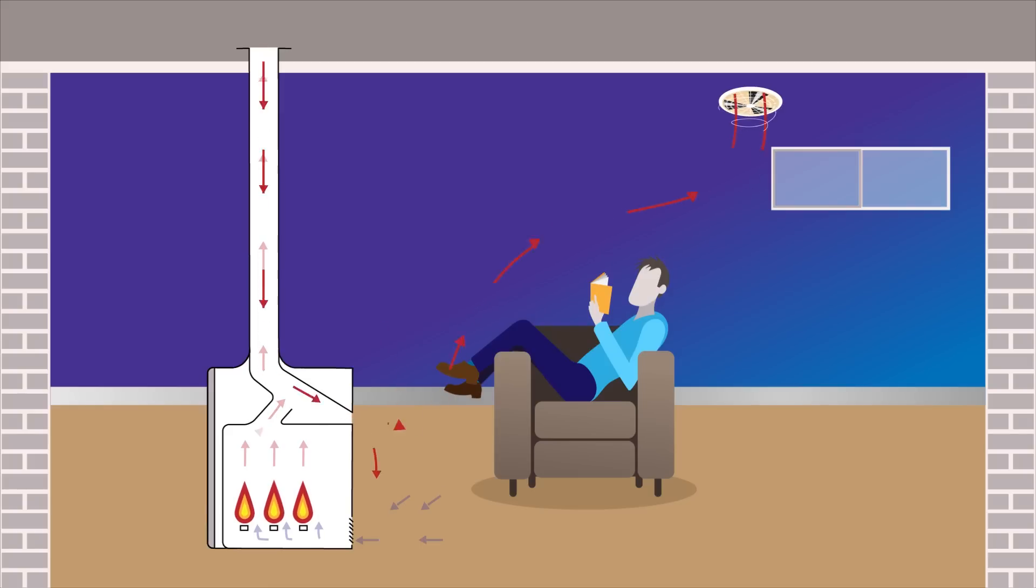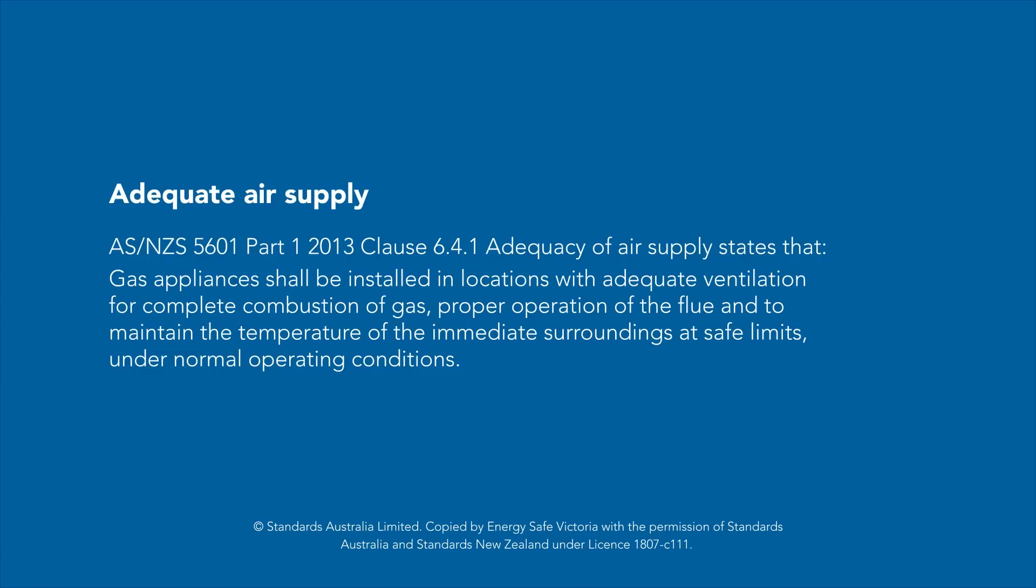This video explains what negative pressure is and its effect on gas appliances. AS NZS 5601 Part 1 2013 Clause 6.4.1 Adequacy of air supply states that gas appliances shall be installed in locations with adequate ventilation for complete combustion of gas, proper operation of the flue, and to maintain the temperature of the immediate surroundings at safe limits under normal operating conditions.